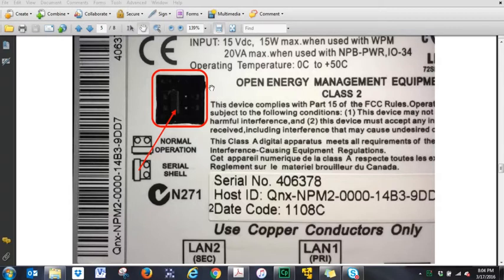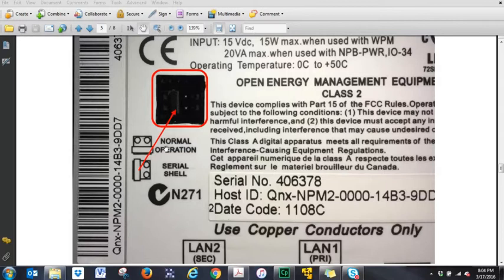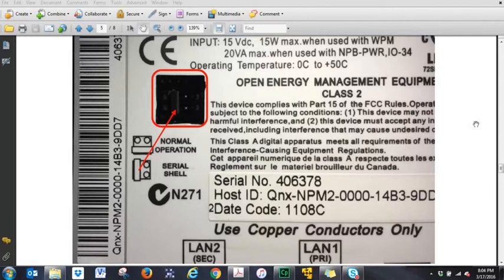By default, when you get a Webstat, only network jack one is active. In order to activate port two, you have to use the serial shell mode on this 9-pin connector. So the first thing you want to do is remove the cover off your Webstat, and it will look something very similar to this. You want to change the jumper that's on the bottom two pins and change it to the left two pins to go into serial shell mode. Also, make sure that your Webstat is powered off.